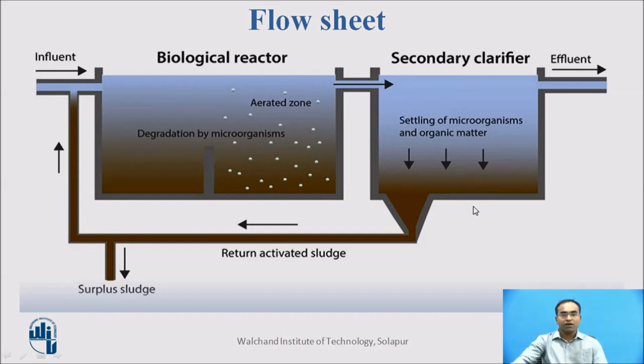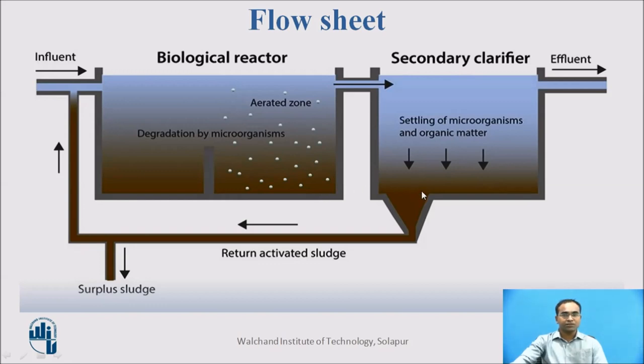After aeration, these microorganisms will come into the sedimentation tank and flocculation and sedimentation happen simultaneously. The sludge collected and settled in the sedimentation tank is taken back. We use activated sludge, so all this settled sludge is the activated sludge. Some portion of the sludge is mixed with the influent and taken back to the aeration tank, and the surplus amount of sludge is taken out from the whole system. Whatever the effluent or clean water present above the sedimentation tank is taken out as effluent.